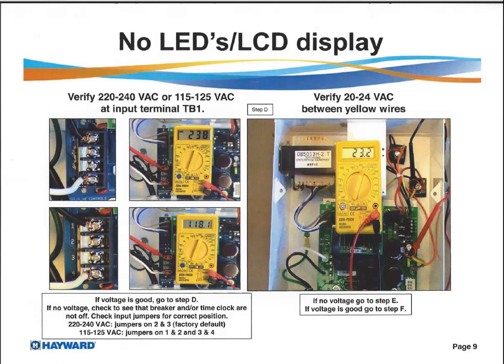This picture should show a red and a black, with 2 stripes on the black. White is usually a neutral. So when I would arbitrarily open this up, I would say it's pre-wired for 115 volts. They should either stripe this red or stripe it black. This is fine, this is normally your hot, and this is normally your neutral. So when you see a white, never assume that it is a neutral, because on this picture right here, it's supplying 110 volts, usually at 20 amps. So never assume anything.